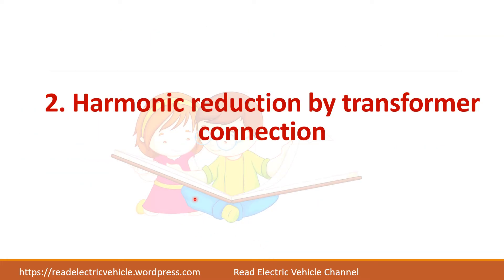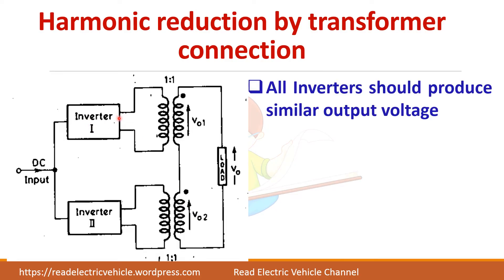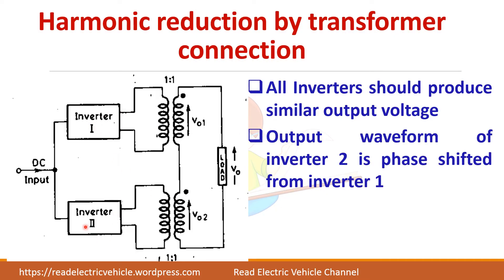The next method is harmonic reduction by using transformer connection. In this method, you need more number of inverters. Here two inverters are taken, but you can take any number. Each inverter output is connected to a transformer and the transformer secondaries are connected in series. All inverters should produce similar output — that is an important condition. The output of one inverter is phase shifted from the other, and depending upon the phase shift, the final resultant voltage changes so that the harmonic content is reduced.